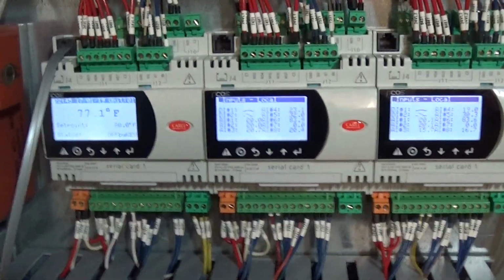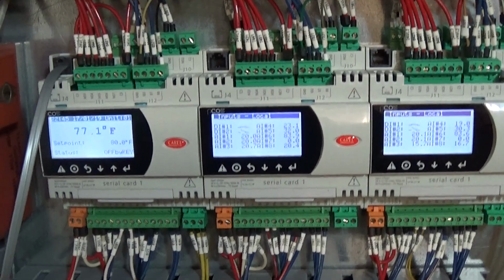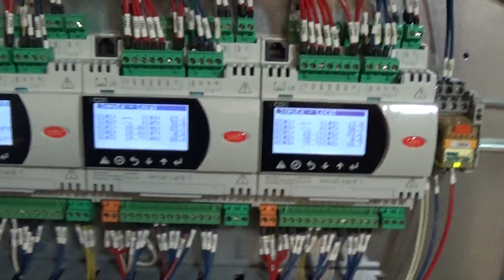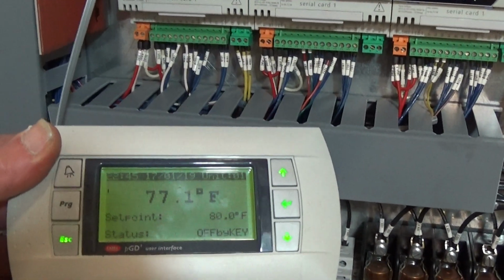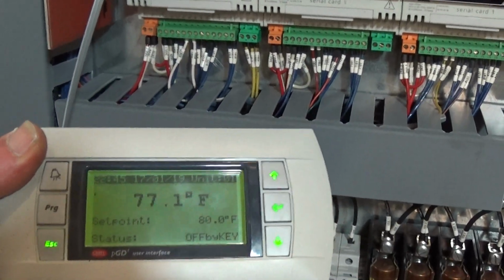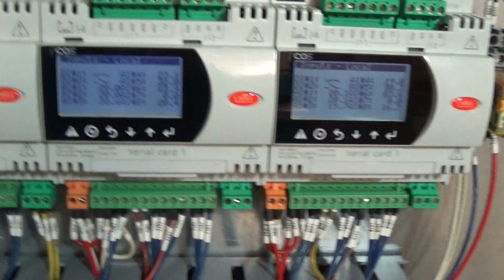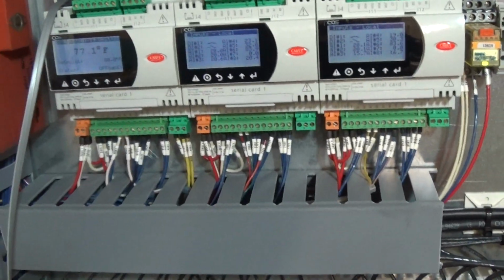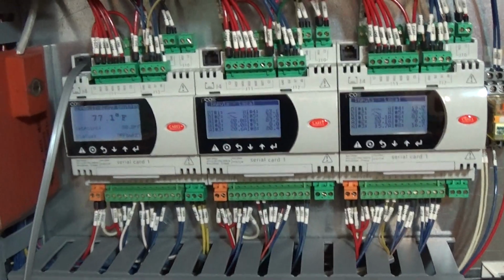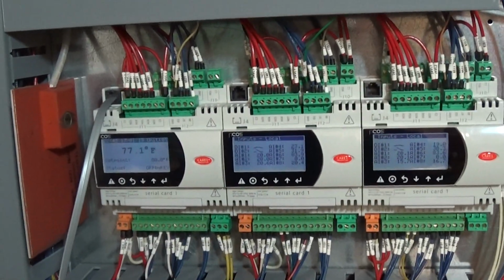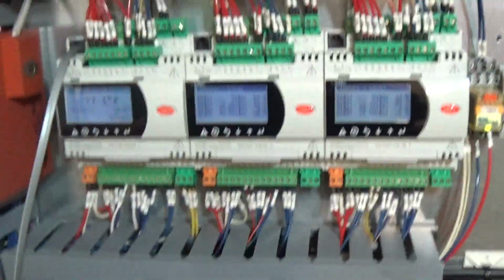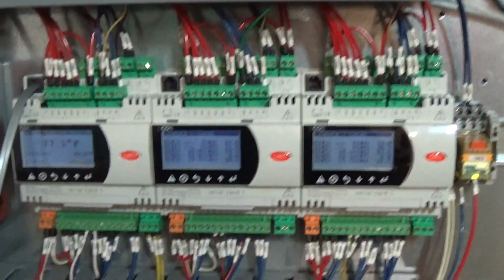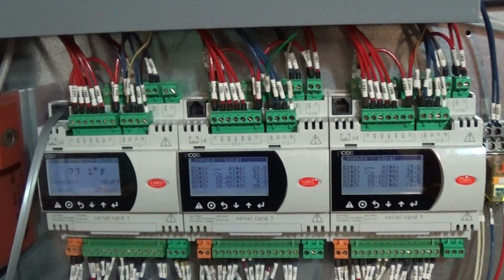So this PLC has one nice feature, whereas this is an outdoor unit and the control is located in the cabinet. It comes with this PGD unit, or pendant unit, that can remotely be placed inside the building. You can pretty much do all the same things you can with the front panel of the PLC itself. So you don't have to be going outside to change any settings or to monitor anything. They normally send that with a 150-foot cable, but somebody nicely cut the end on us. So we bought a 20-foot cable so that we could power that up. You can always get a longer cable if you need to.